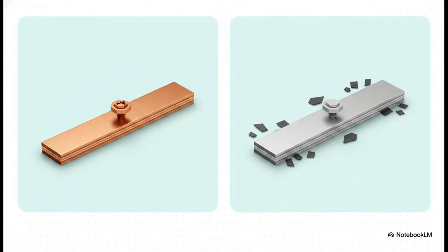When designing these systems, the big material showdown is almost always between copper and aluminum. And this brilliantly illustrates the real-world trade-offs engineers have to make. Copper is pretty much the default. It's got about 100% IACS conductivity, lets you build highly compact layouts, and offers incredibly strong joint stability. Aluminum, on the flip side, sits at about 61% conductivity, which means it needs a larger cross-section to hit the same resistance. But it gives you a much lower mass and material cost. That weight reduction comes with a catch, though. Aluminum requires much more demanding joint practices because of this rapid oxide film buildup.